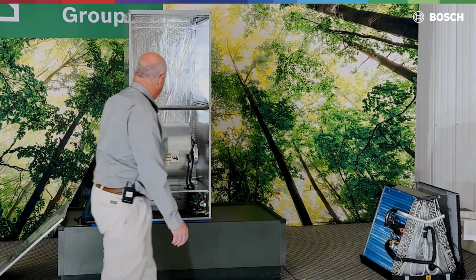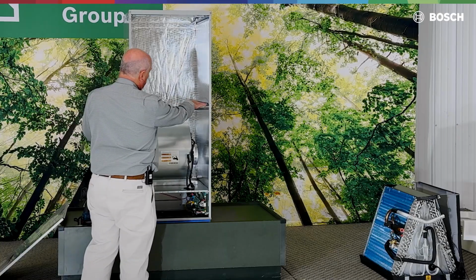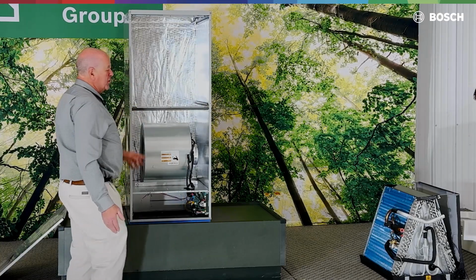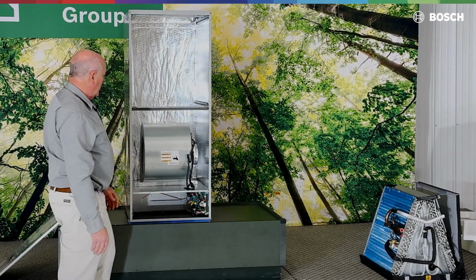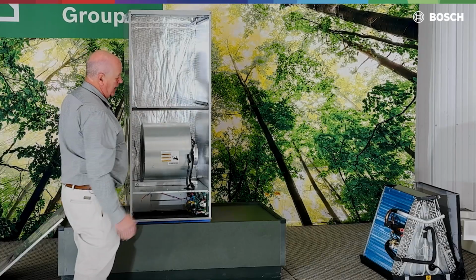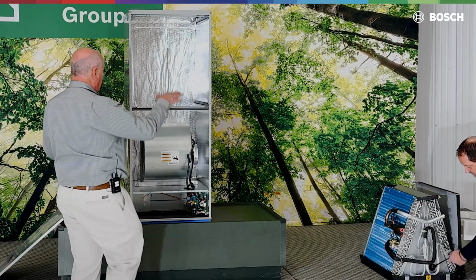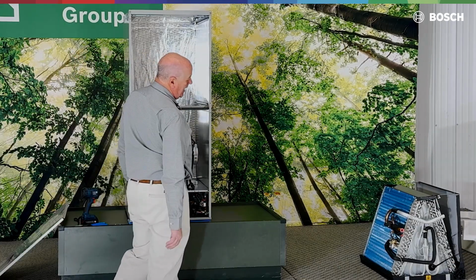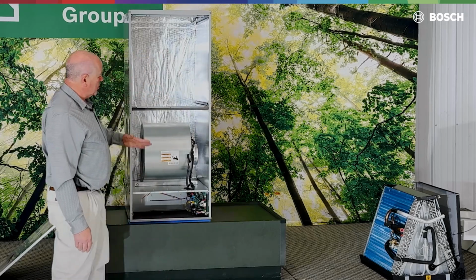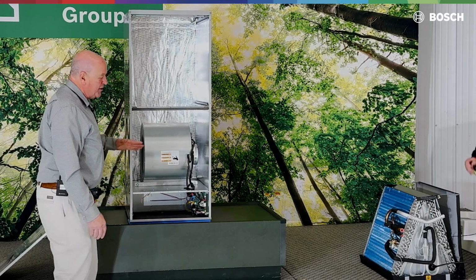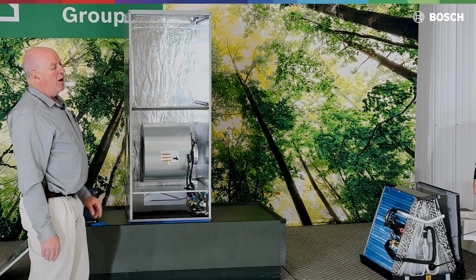Gentlemen, we have rails that this coil must slide into, and something that's kind of important: these units need to be relatively level, left to right for sure. If it's leaning one way or the other, water may not drain out of that pan. We will suggest a slight lean to the front so any water in the pan drains. We don't want water staying in the pan.